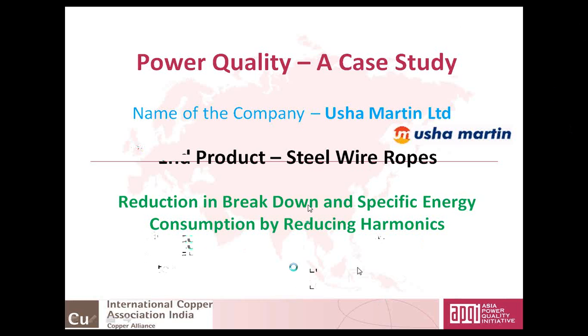Actually, what is the problem due to this disturbance? In my plant, we were having high failure of electrical equipment. There were many breakdowns of electrical motors, PLCs and drives. I mentioned this on the slide. We were not able to pinpoint the root cause of these electrical breakdowns. There may be many root causes for the breakdowns. Those root causes were addressed one by one, even though the problem was not reduced that much.